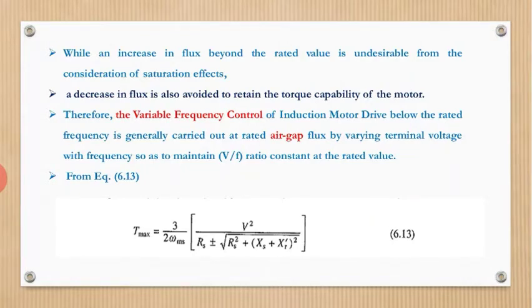As already discussed, flux beyond the rated value is undesirable from the consideration of saturation effect, so we can't go beyond the rated value of flux. A decrease in flux is also avoided to retain the torque capability of the motor. If flux is decreased, the torque capability of the motor is reduced, so we should avoid that as well.